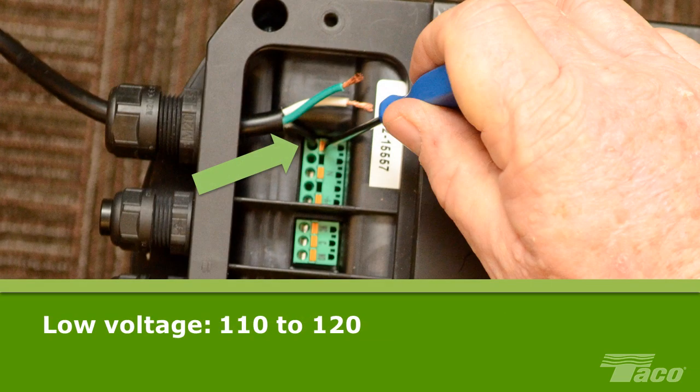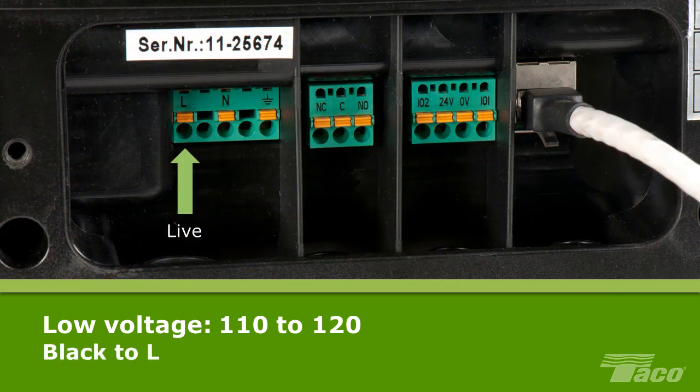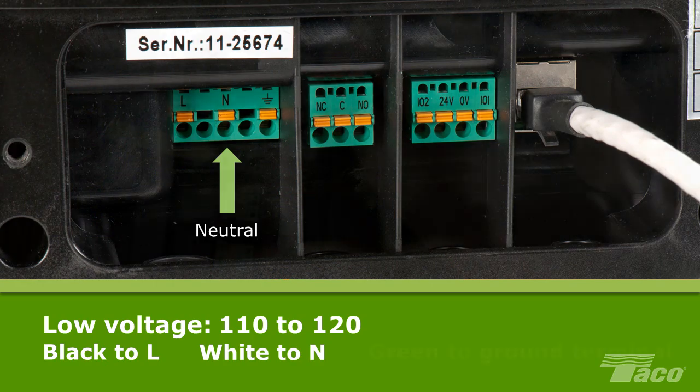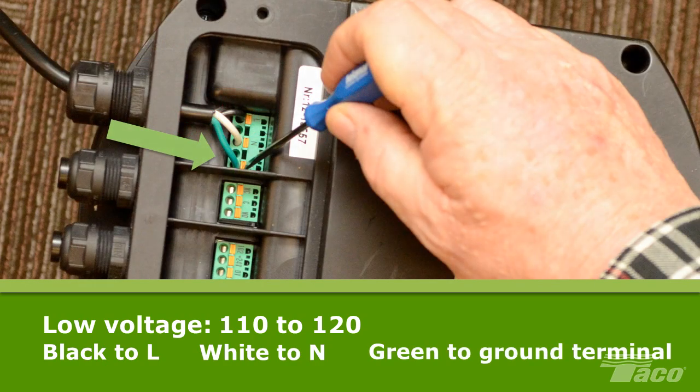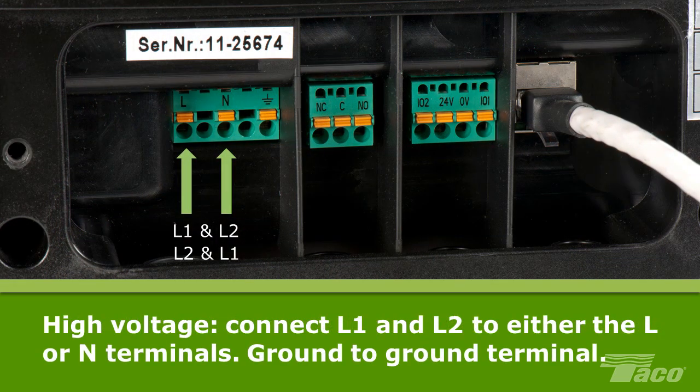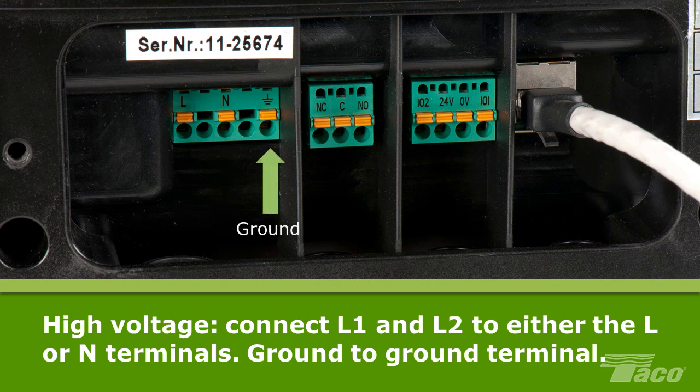For low voltage 110 to 120 volt single phase power, connect the 3 wires of the power cord to the corresponding labeled electrical terminals: the black positive wire to L, the white neutral wire to N, and the green ground wire to the ground terminal, using the quick connect push down connectors. For high voltage 200 to 240 volt single phase power, L1 and L2 can be connected to either the L or N terminals and the ground wire to the ground connection.